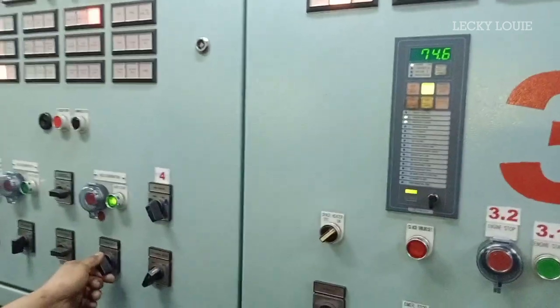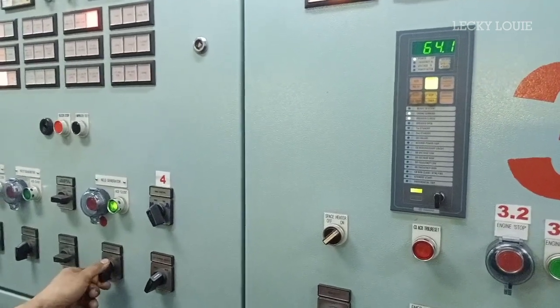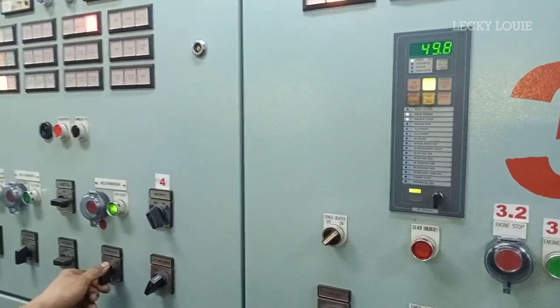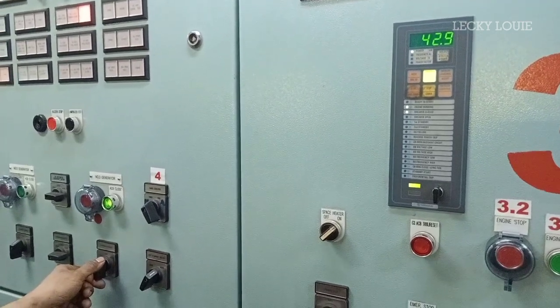When the load is already negative 75 kilowatts, we just need to wait for the time delay to activate the reverse power protection.